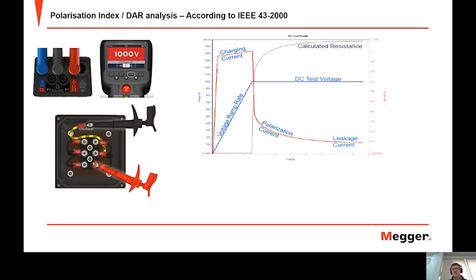What we're looking for with the PI test is for the dipoles in the insulation to polarize as we apply the DC voltage. And we're looking for contamination and moisture, which could be shown by a low PI ratio. But it's really a trending tool. We wouldn't take the motor out of service because it has a low PI test necessarily. We would trend it, or potentially we would dry the machine and retest it to see if it's a moisture problem.